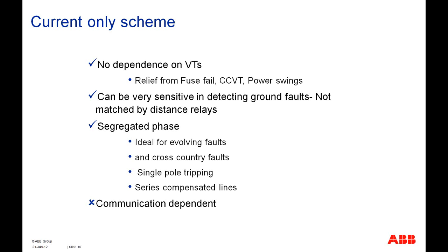As line differential protection is basically a current-only scheme, there is no dependency on the VTs. So we do not have to worry about fuse failure protection, CCVT issues, or power swing issues. VTs can be connected in a line differential protection scheme, but just for measurement purposes; the main line differential protection does not really take care of the voltage information. And it can be very sensitive in detecting ground faults, and we will talk about how we can detect very sensitive ground faults by using this line differential protection scheme.